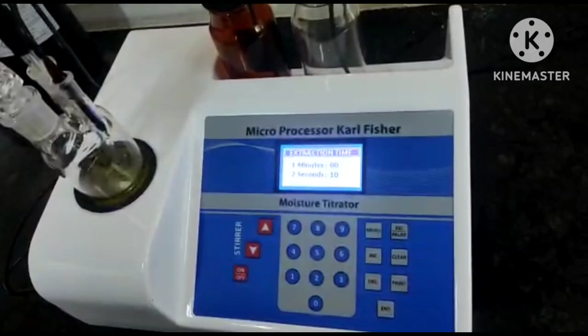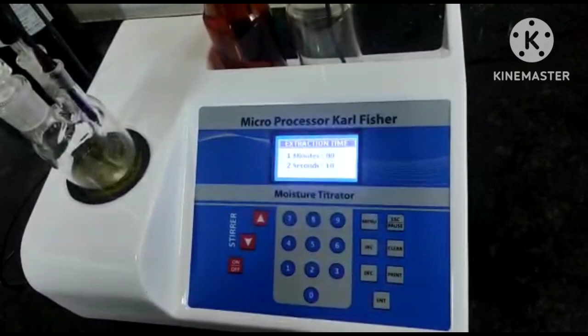If we are putting distilled water, then it should be extracted for 10 seconds, which is what we have selected right now. If we have powder or something in crystal form, then you have to increase the extraction time. It should be around 2 minutes or 4 minutes. So we can select according to our type of sample.